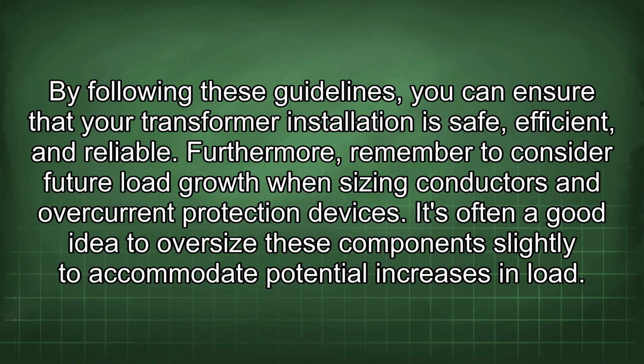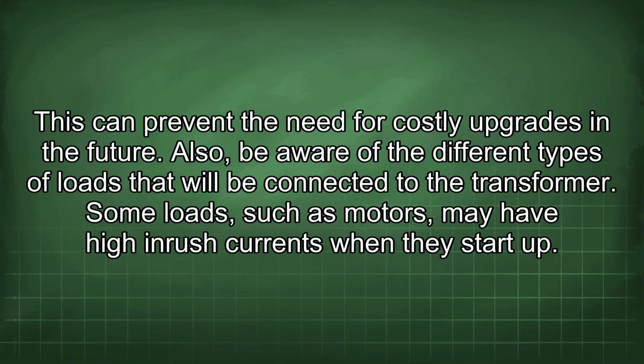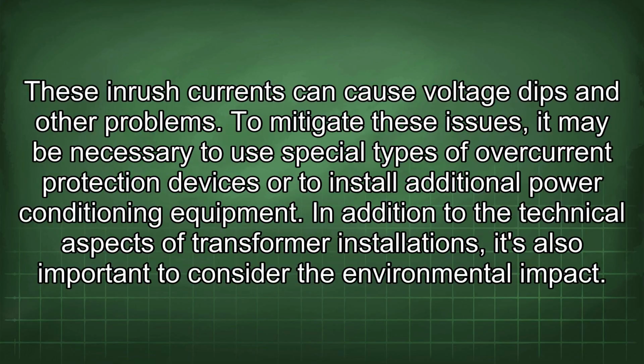Furthermore, remember to consider future load growth when sizing conductors and overcurrent protection devices. It's often a good idea to oversize these components slightly to accommodate potential increases in load. This can prevent the need for costly upgrades in the future. Also, be aware of the different types of loads that will be connected to the transformer. Some loads, such as motors, may have high inrush currents when they start up. These inrush currents can cause voltage dips and other problems. To mitigate these issues, it may be necessary to use special types of overcurrent protection devices or to install additional power conditioning equipment.